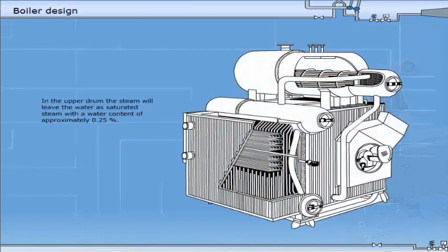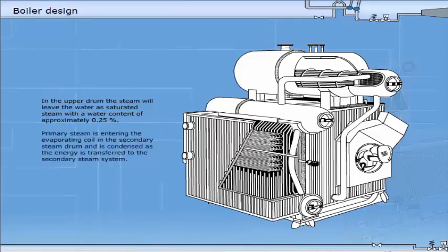In the upper drum, the steam will leave the water as saturated steam with a water content of approximately 0.25%. Primary steam is entering the evaporating coil in the secondary steam drum and is condensed as the energy is transferred to the secondary steam system.